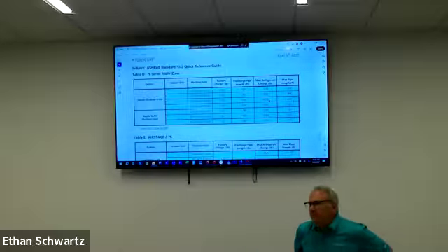So if you have a 10 by 10 bedroom that you're putting one of those units in, unless they have a tall ceiling and you're mounting that wall mount high, you can have 8.6 pounds without any ventilation. See how this is working? But if you have that 10 by 12 room, roughly, or 10.5 by 12, and you mount that thing at 6 feet, because when we go back down to the bottom of this, it's 6.38, but that's at maximum. So when you're out quoting, you're going to look at that. Everybody see how that's working? I don't want anybody to get nervous about it, but it's just got to have that extra check on the job site. Plus you can get credit for ventilation if you add it in.